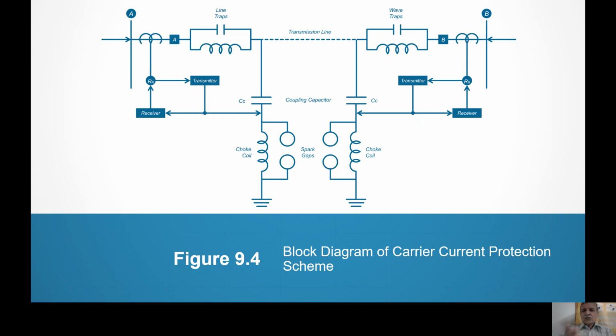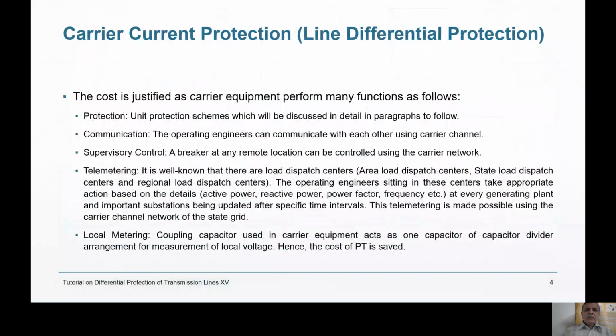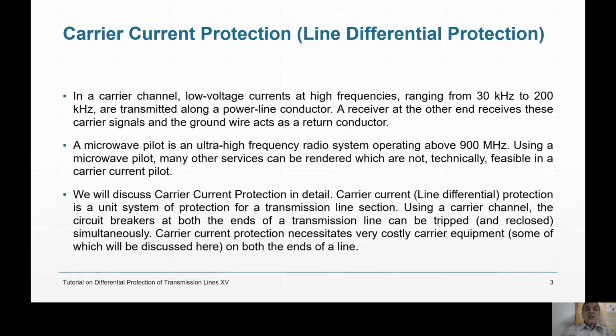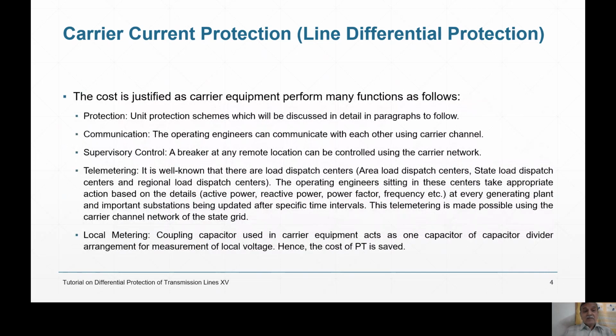So I have shown you how A and B will simultaneously trip, right? Similarly from B to A, if there is a fault near B, then B will trip locally and it will send a carrier signal to A. So that can be done. Some write-up with reference to that is written. The cost is very high. The cost of this equipment is very high.